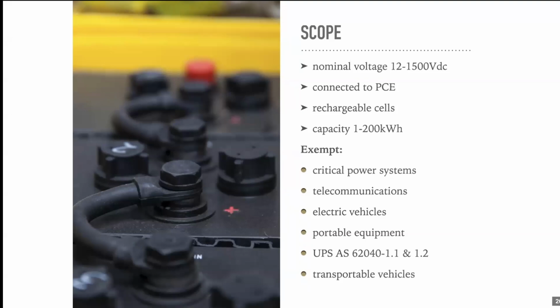So transportable vehicles are covered by other standards, ASNZS 3001, for instance. So you only have to comply with that standard, not with this one, for transportable vehicles. I jokingly point out that maybe if you put wheels on your battery, it's not covered by the standard, something like a car. Anyway, let's go back to the top of that list. Nominal voltage range of 12 to 1500 volts DC. We're capturing a very wide range of battery systems there.